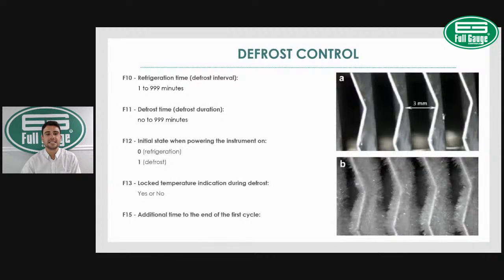and additional time to the end of the first cycle. This is a good feature to desynchronize defrost cycles when you have multiple pieces of equipment. So let's say we have 5 coolers in one installation. We don't want those coolers to enter defrost at the same time. Let's say we set the coolers for 6 hours refrigeration and 30 minutes defrost, and they all start together.